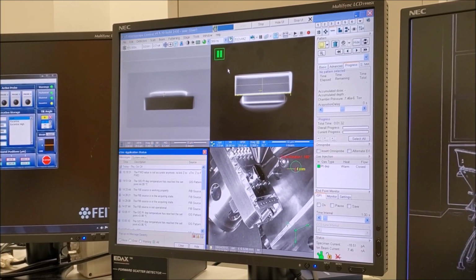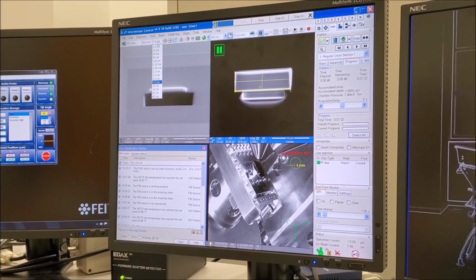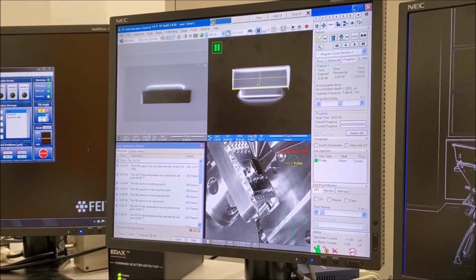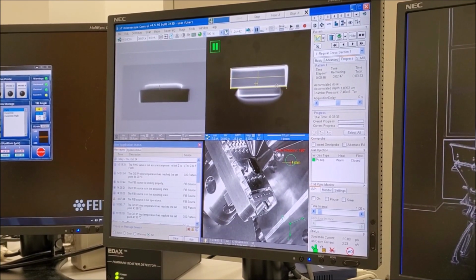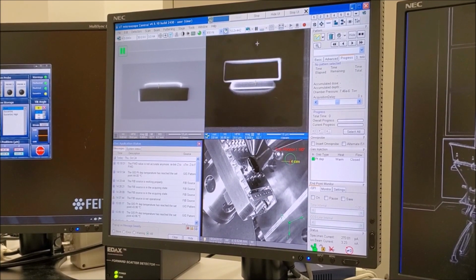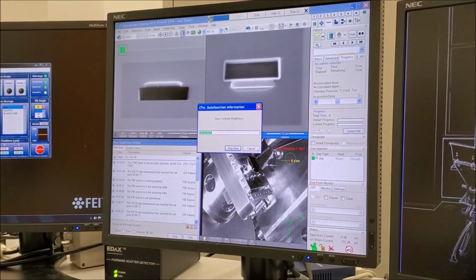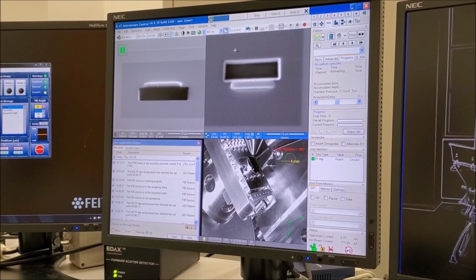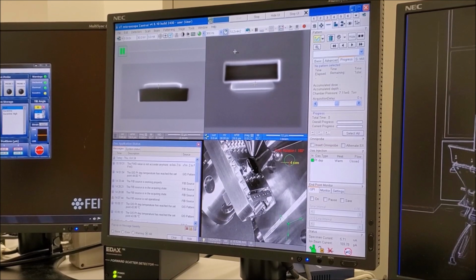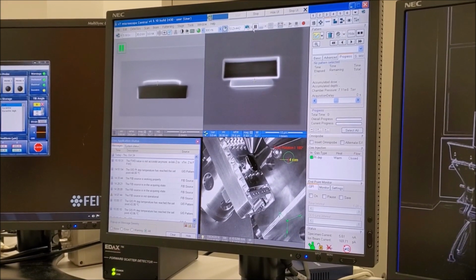To perform a cleaning cross-section, activate the ion beam quad and change the current as needed. Then delete any patterns present in the ion beam quad. Unpause the ion beam image to go live, perform auto contrast and brightness, and focus the image as needed. When finished, acquire a snapshot.